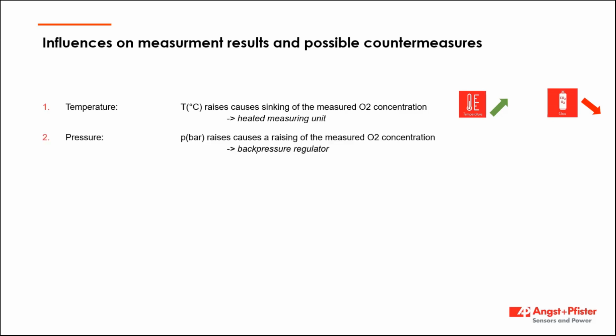Another very important influence is the pressure. Here it's exactly the other way around to the temperature, because if you have a higher pressure within your gas path, the oxygen molecules will be compressed, and therefore you will have more oxygen molecules between those pole shoes. The sensor itself measures more oxygen, even though within the whole gas you have the same amount of oxygen. So if the pressure rises, the signal of oxygen measured will rise too.